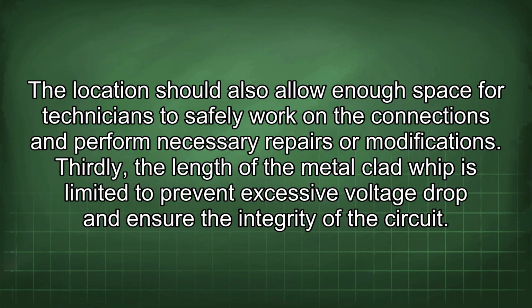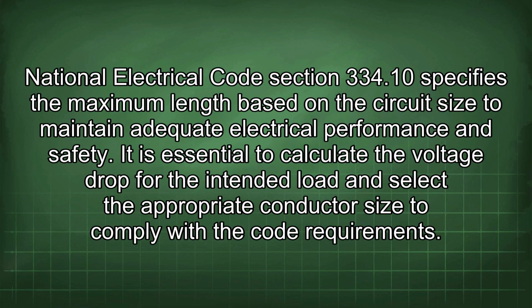modifications. Thirdly, the length of the metal-clad whip is limited to prevent excessive voltage drop and ensure the integrity of the circuit. National Electrical Code Section 334.10 specifies the maximum length based on the circuit size to maintain adequate electrical performance and safety. It is essential to calculate the voltage drop for the intended load and select the appropriate conductor size to comply with the code requirement.